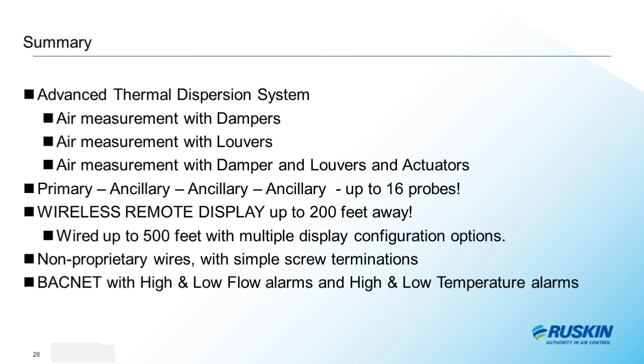Wireless remote display farther away from the air measurement station than ever before possible. Wired remote primary controller or remote display up to 500 feet away on the probe network using our recommended ConnectAir cable. This is a wire that's available from your local wire supplier or from your Ruskin representative in convenient 500-foot rolls. Phoenix screw terminal connections are the highest quality connector, greatly simplifying installations and providing reliable, trouble-free connections. And while I didn't spend any time on this, we have the ability with this product to generate 4 alarms via the BACnet interface. We have low flow alarm, high flow alarm, low temperature alarm, and high temperature alarm. Technical material for another presentation.